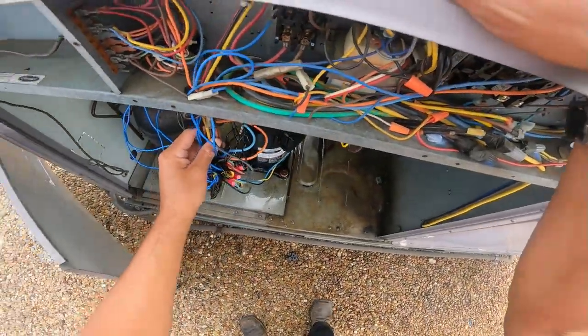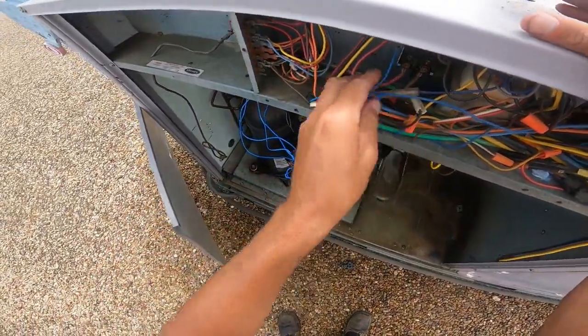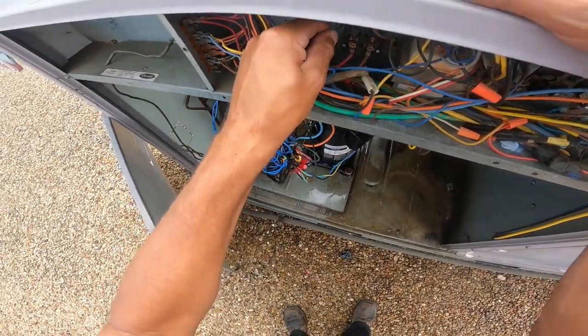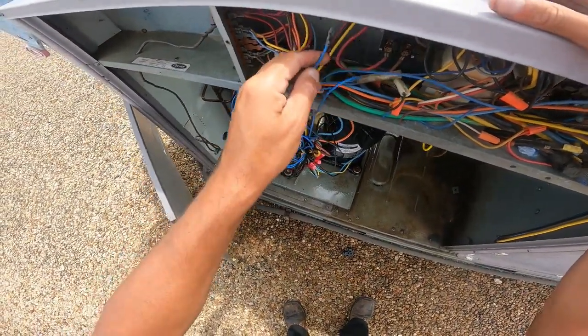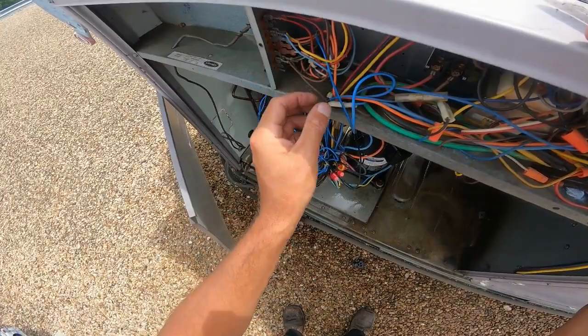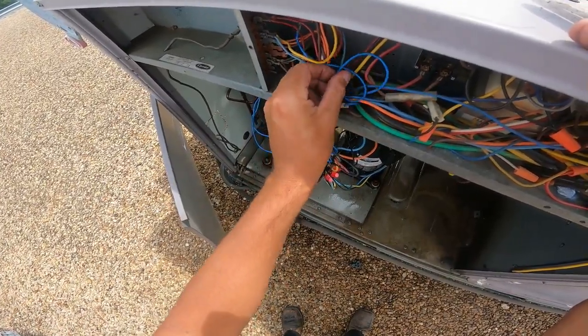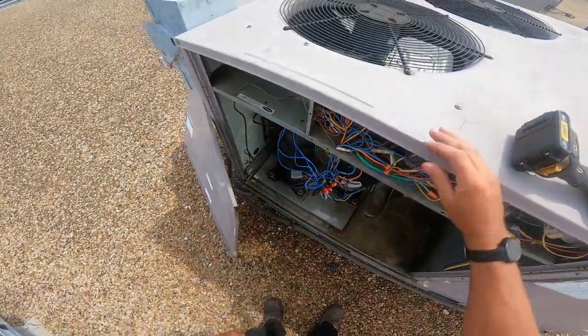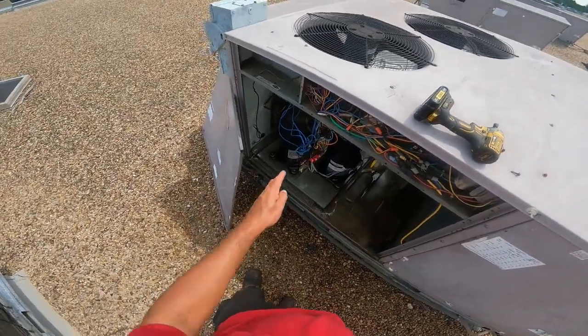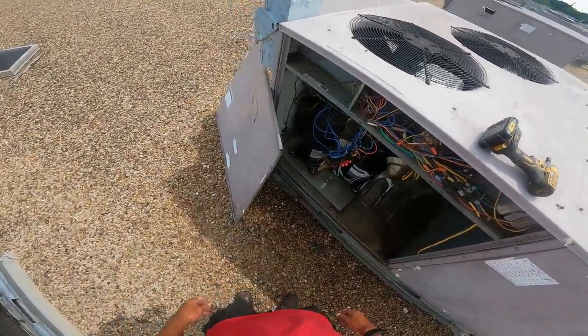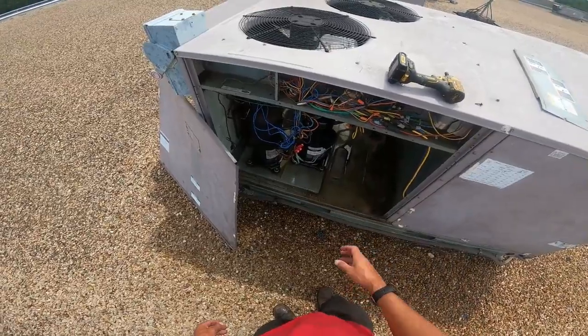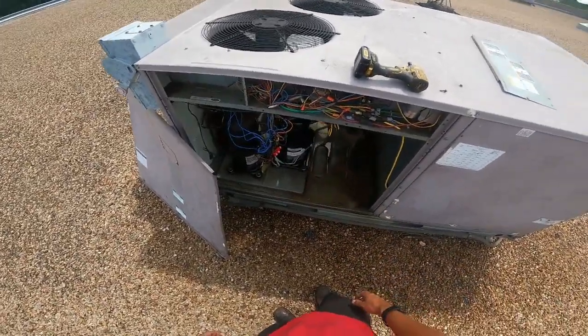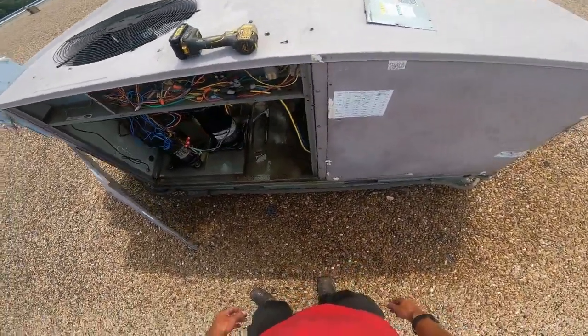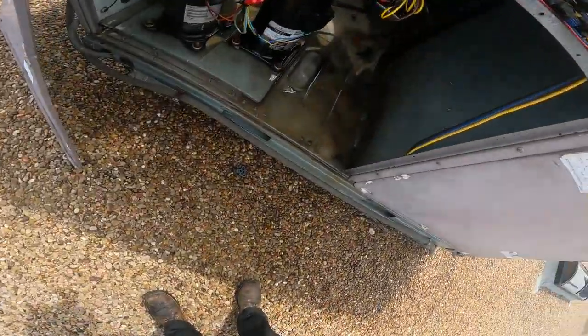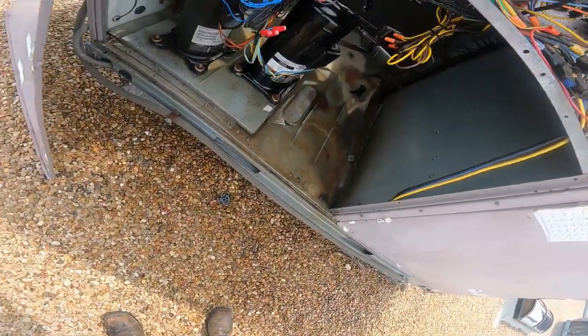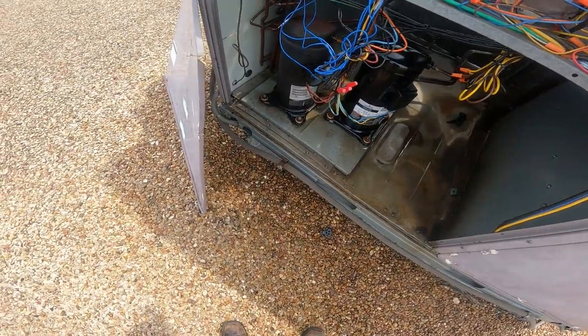That's this contactor right here. So all I'm going to do is disconnect my hot. We're going to tuck it in over here so it doesn't arc on anything, and we're going to turn this thing back on and let it run. But that's a quote, it's going to need a dryer and it's going to need to be flushed. Whenever refrigerant blows out like that, it causes the oil to go places it isn't supposed to be, so there's a good chance the feeder tubes are just clogged up with oil.